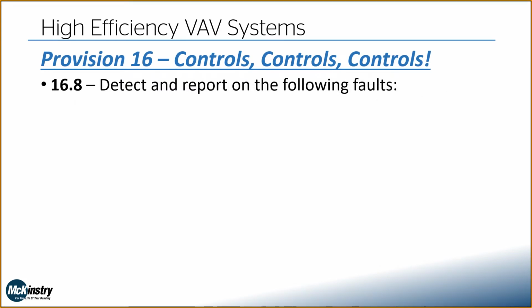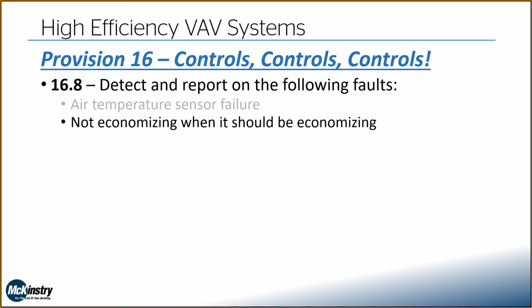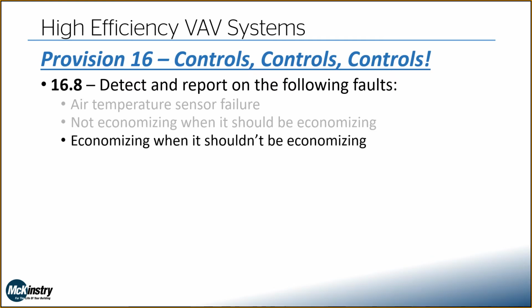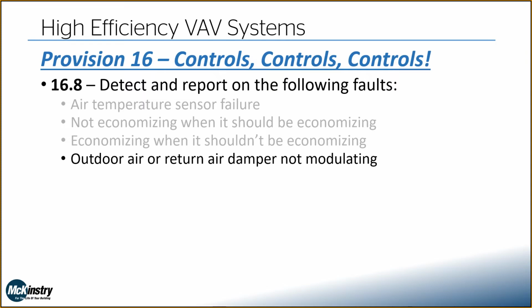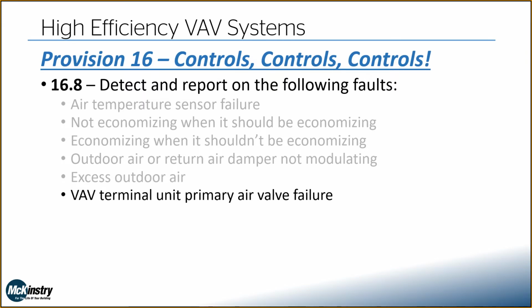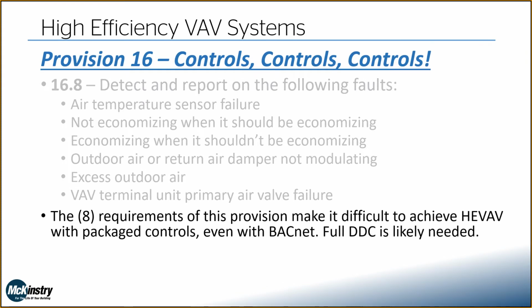And lastly, we have a number of faults and alarms we need to detect and report. We have to say when a temperature sensor has failed, when we're not economizing when we should, or economizing when we shouldn't be. Outdoor air or return air dampers not modulating as they should. If we're bringing in excessive outdoor air, and if our VAV has a primary air valve failure, as noted by that sequence on the previous slide where we're driving the box open and closed. So these are the 8 requirements of this one provision.